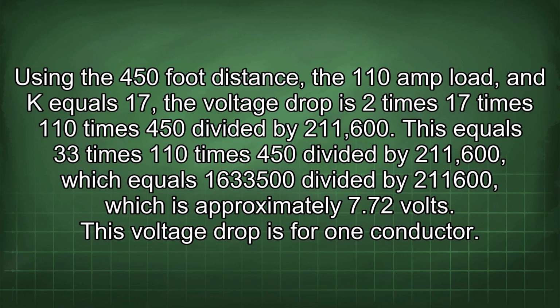times 17 times 110 times 450 divided by 211,600. This equals 33 times 110 times 450 divided by 211,600, which equals 1,633,500 divided by 211,600, which is approximately 7.72 volts. This voltage drop is for one conductor.